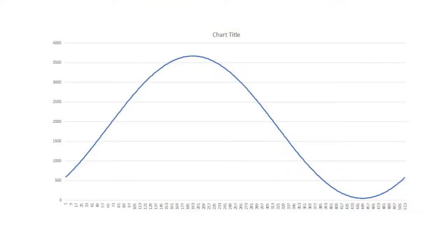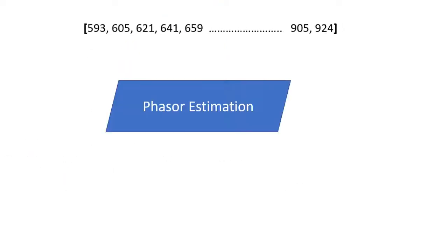It takes 512 data points in one power cycle for estimating highly accurate phasor parameters. And each loop of phasor estimation block uses half cycle data to produce a phasor value and later time tag it.